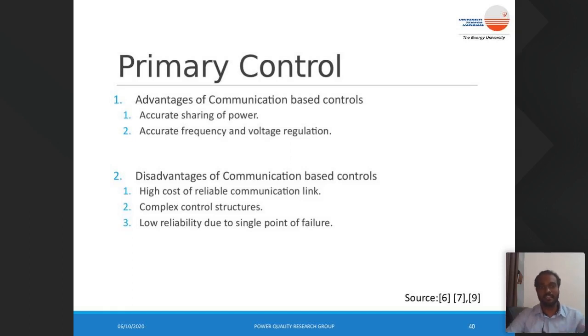I have said it simply in the previous slide, but when you look deeply into all those control strategies, these communication-based control strategies are quite complex in nature as compared to the decentralized one, which we'll discuss later. And they have low reliability because they are vulnerable to a single point of failure. If the communication channel fails, there is no way to share the power command from the centralized controller to the sources. So these are the disadvantages of centralized control.